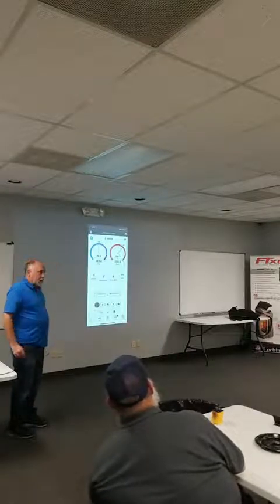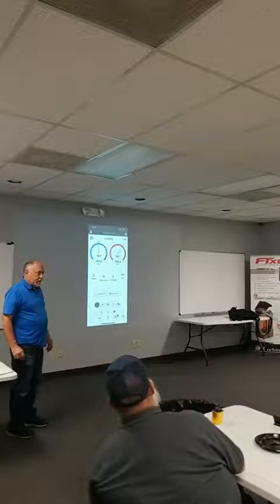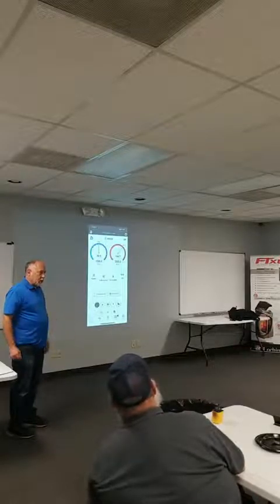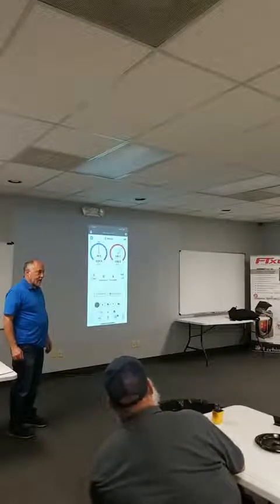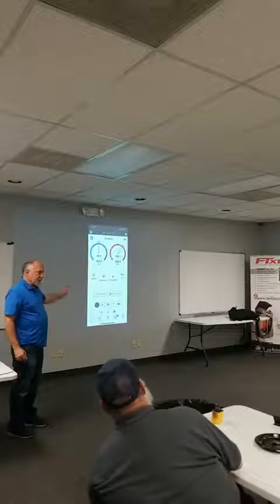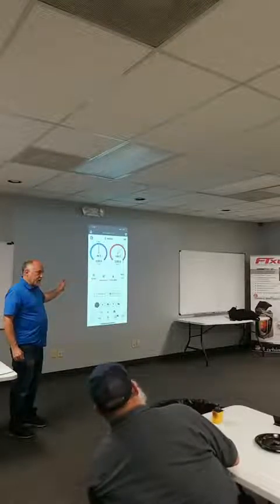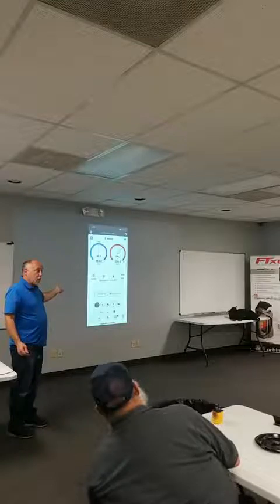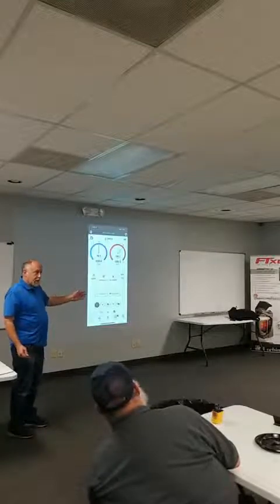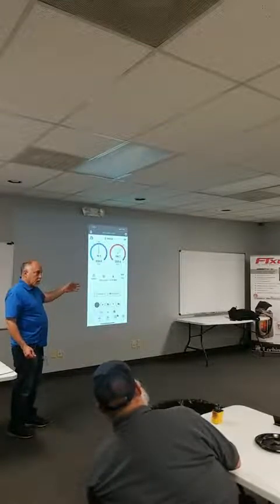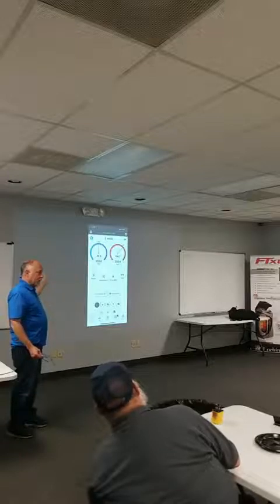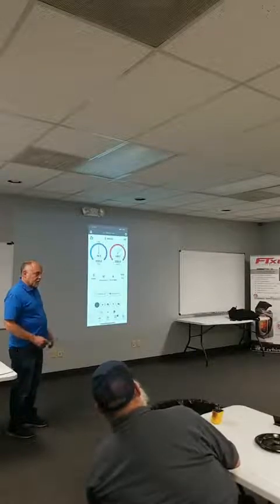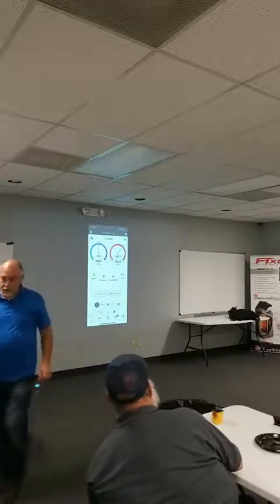But if you can't tell me what the pressure should be, then you just lost two of your primary drivers for that diagnostic chart, right? Most guys can't tell you what the pressure should be on the machine. They just don't know. They can tell you if it's really high or really low, but they can't tell you if it's a little high or a little low. They can't tell you what's going to happen if I raise the airflow, how it affects the suction pressure, or humidity, or anything else.